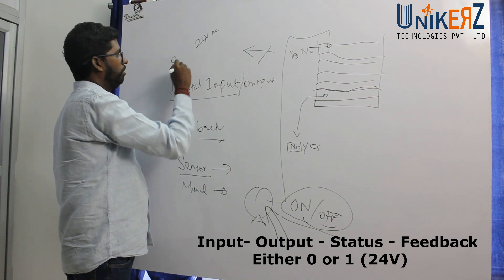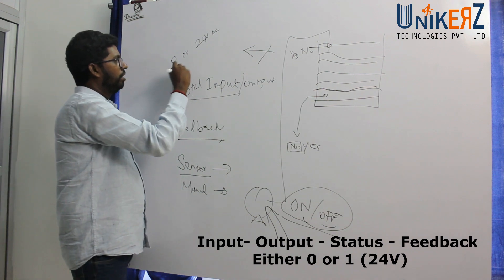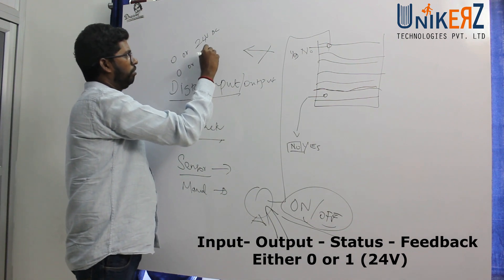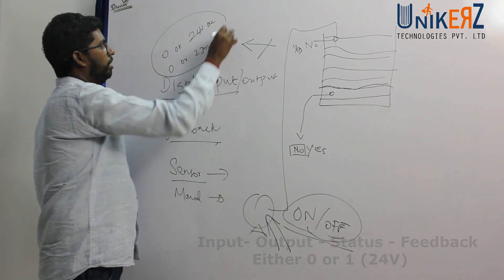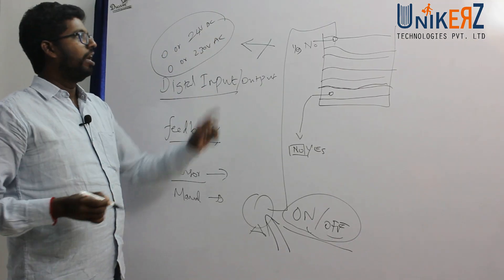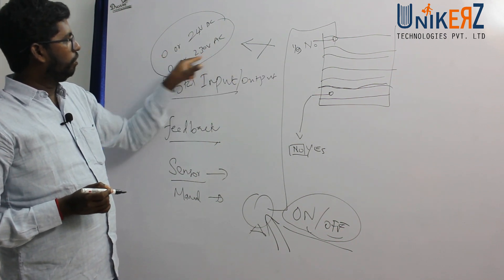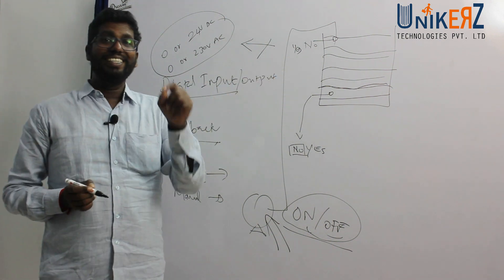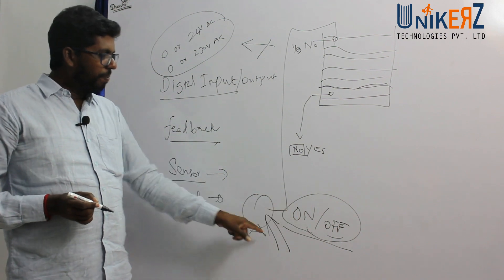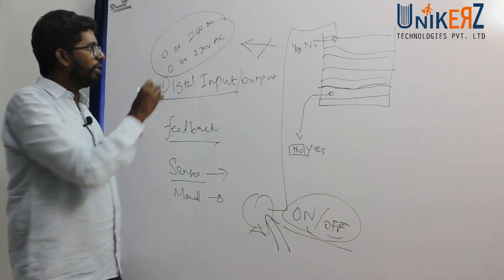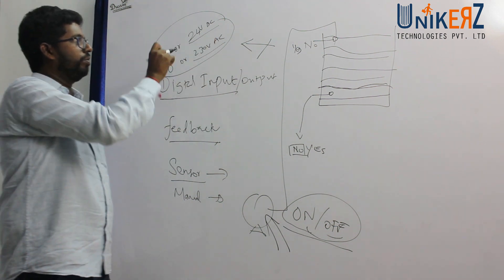That is zero or 24V DC, or zero or 230V AC — this is what discrete means. The feedback is that voltage is either coming or not. That is the digital input. And that is the digital output — the on command for the pump is 24V DC or 230V AC.